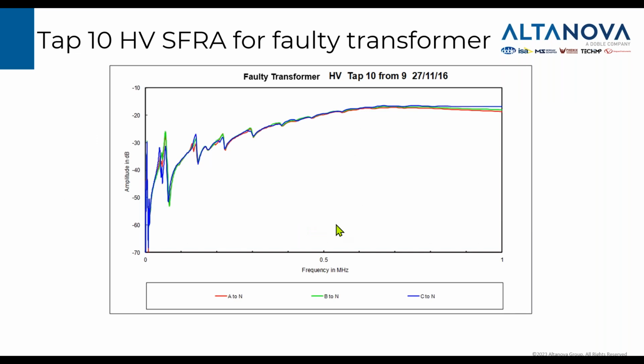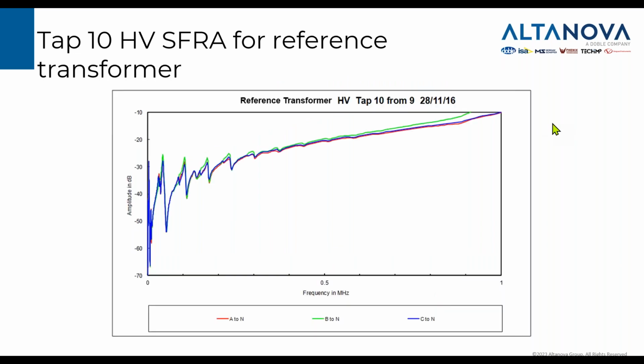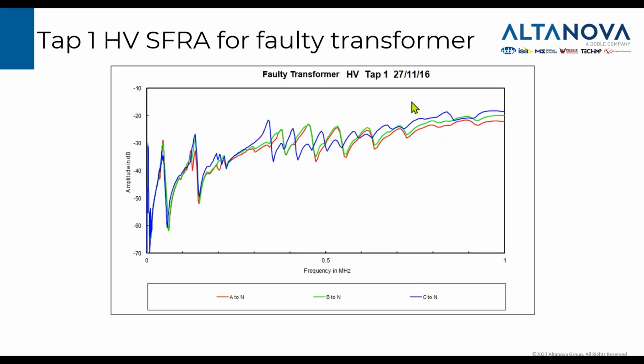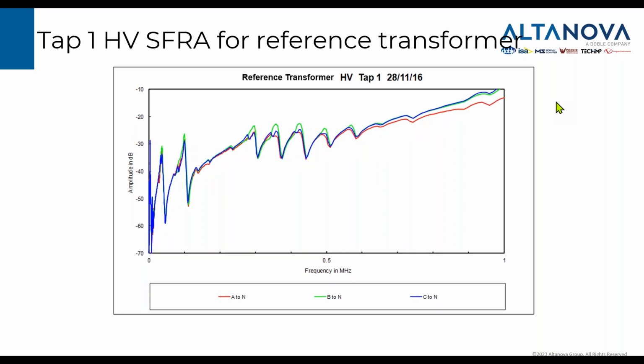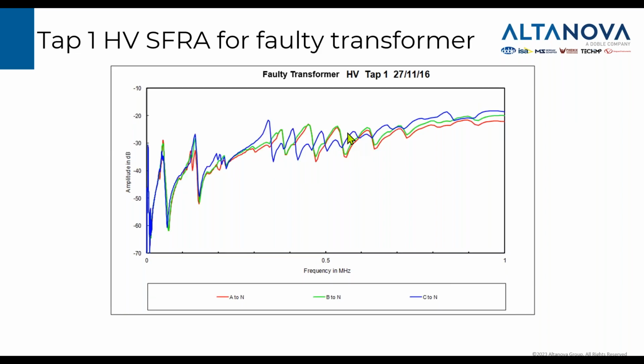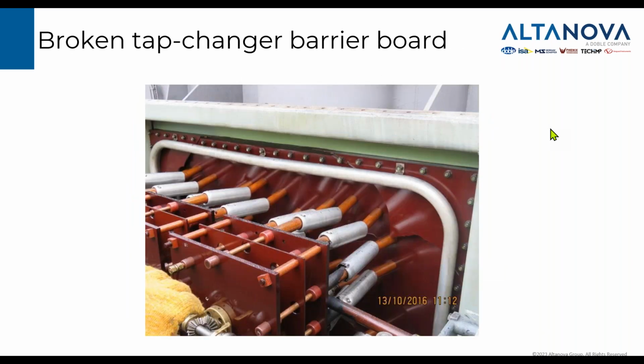So this is what we had. This is our measurement on tap 10, which means without any tap winding included. This is measured on the faulty transformer, and this is our reference transformer, the sister transformer of the same design. Then this is measured on tap 1 where the regulating winding is included in the measurements. And we can see the C phase is much different than the other two. And this is our reference on tap 1. There is no such effect like here. So we saw the C phase was really the one which was affected.